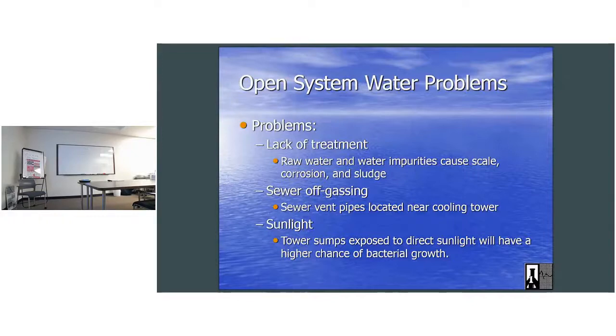They couldn't get it. That piping, it was in a big hospital, so they ripped out a centrifugal and put in a Climacool side by side with the existing centrifugal. There were several problems with doing that, but that piping was just so old and nasty. They replaced the tower. They tried, I don't know what all. U.S. Water was down there for a long time, but they ended up abandoning that.